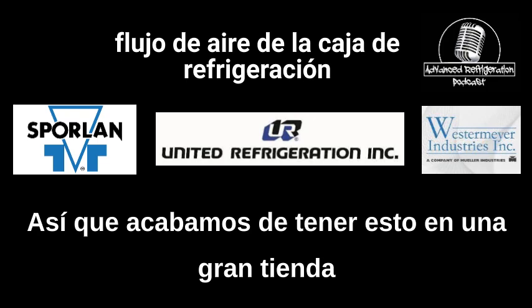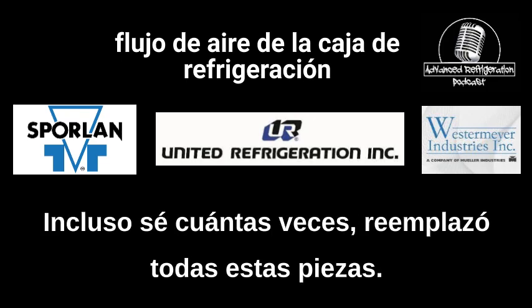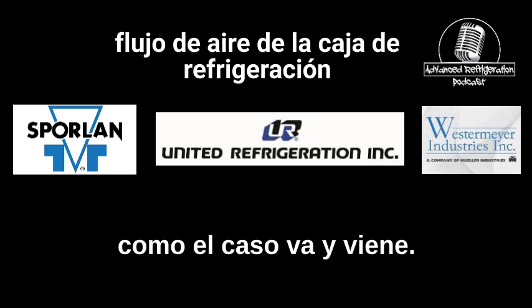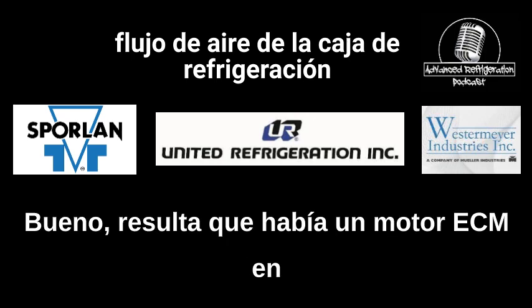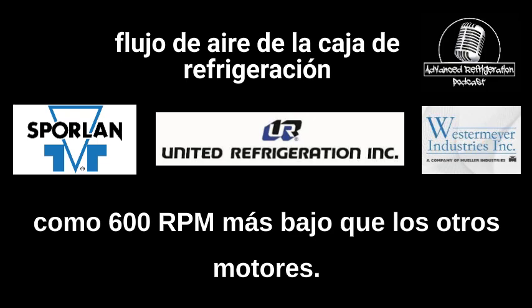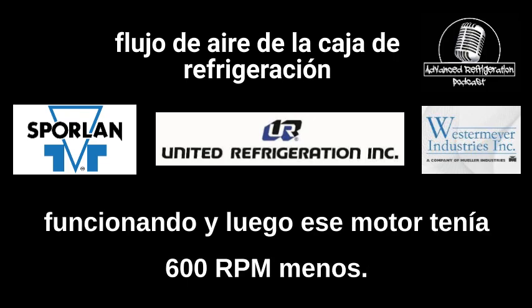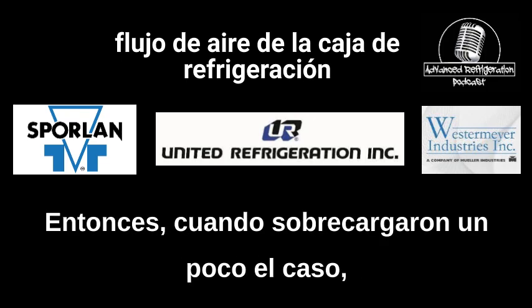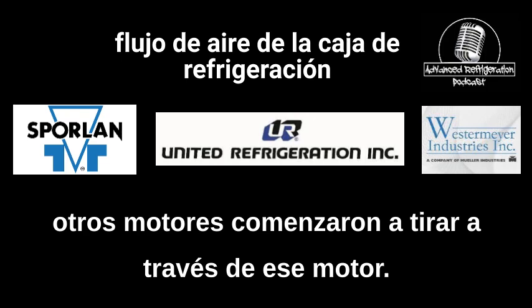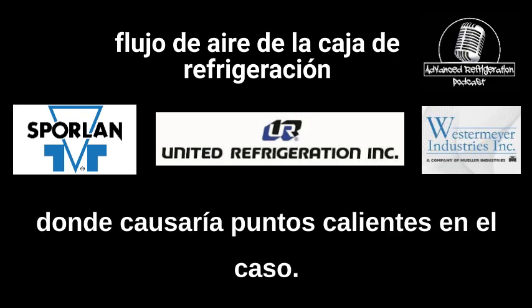So we just had this at a big box store using glycol, and the service department was out there I don't even know how many times, replaced all these parts, and I've been saying it's airflow for months now, and they've been saying the case comes and goes. Well, it turns out there was one ECM motor in the center of the case that the manufacturer had set like 600 RPMs lower than the other motors. So what was happening is the other motors were running, and then that motor was 600 RPMs less. So when they overloaded the case a little bit, it put a little bit more strain on the return and increased the static pressure. And then the other motors started pulling through that motor. So it ended up messing up the airflow enough to cause warm spots in the case.